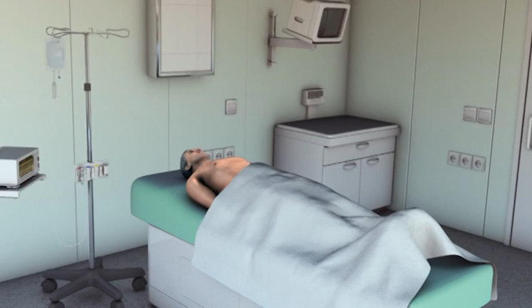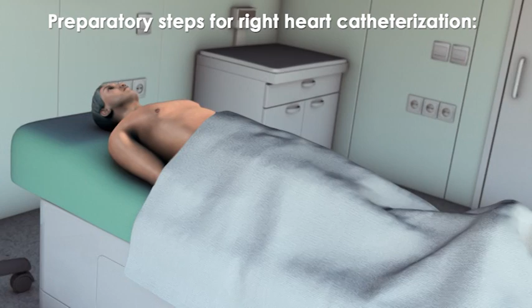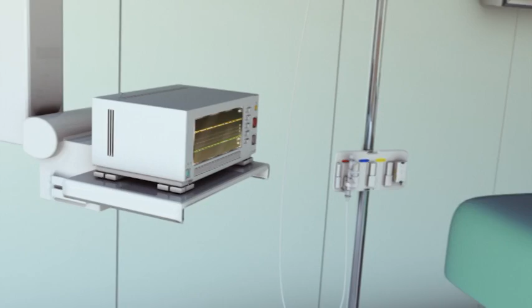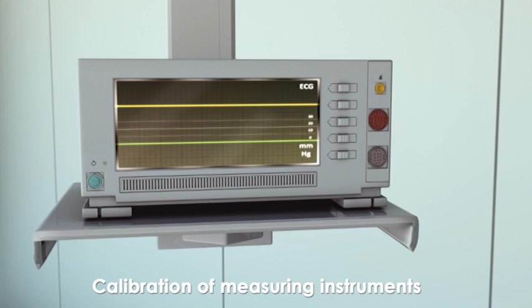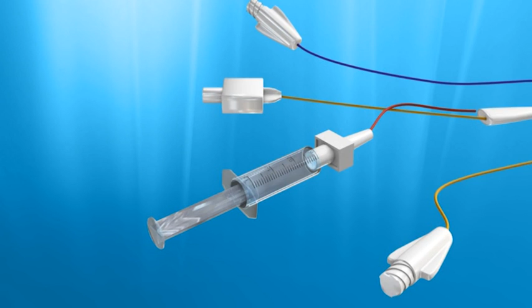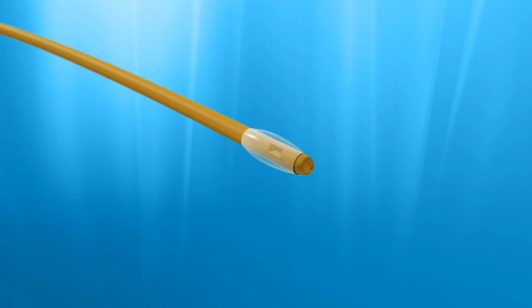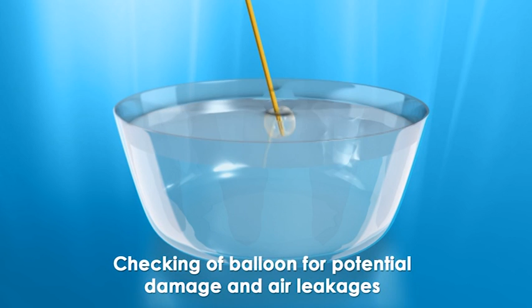Before the right heart catheter can be inserted into an appropriate vein, several preparatory steps have to be taken to ensure the RHC's working order and the correct positioning of the patient. The measuring instruments have to be calibrated following the manufacturer's guidelines. The inflatable balloon at the tip of the RHC must be checked for potential damage and air leakages. This can be done by immersing the inflated balloon in a sterile solution. After insertion, a rupture of the balloon during inflation would cause air embolism.